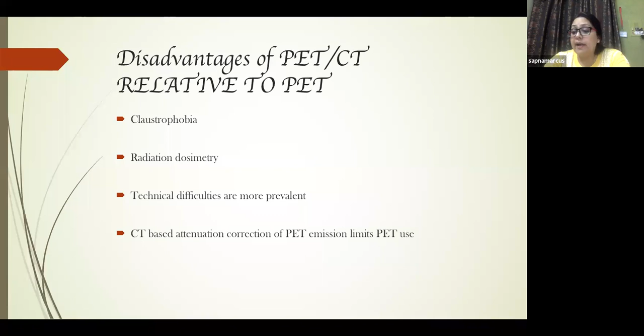Now, radiation dosimetry. There is a lot of radiation exposure, 5 to 10 times more, whereas in PET only it is 3 to 5 times the background radiation. Technical difficulties are more prevalent in PET CT as compared to PET. If one component, for example the CT, is down, then the whole PET CT is down. CT based attenuation correction of PET limits the PET use. So these technical glitches have to be looked after when you are trying to write PET CT. It's not an easy job when you are writing a fusion image.